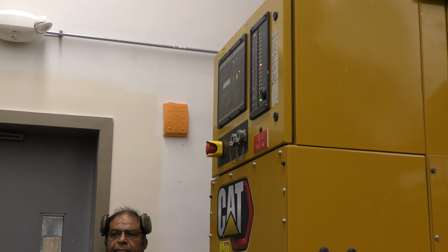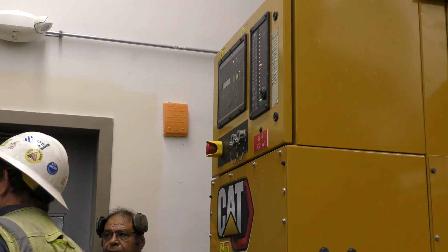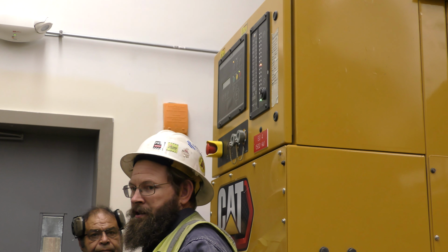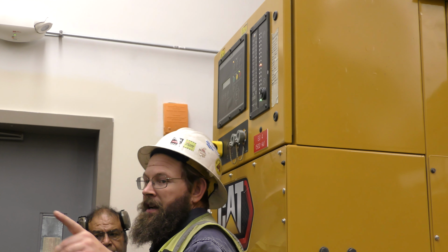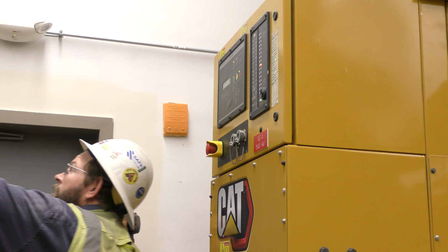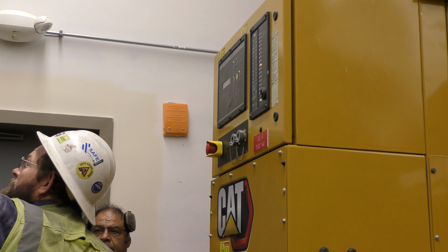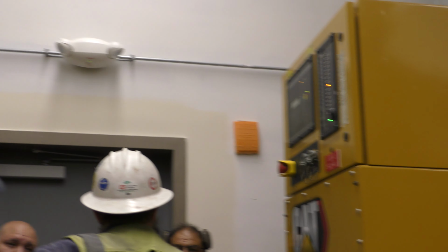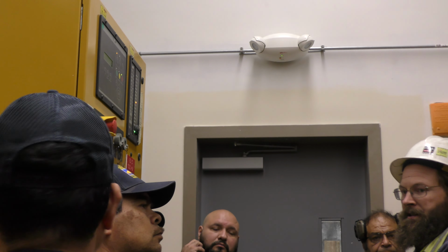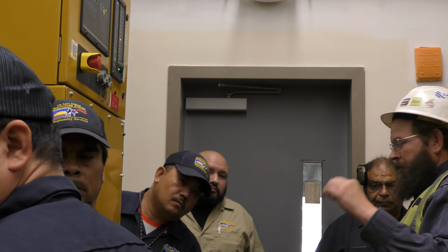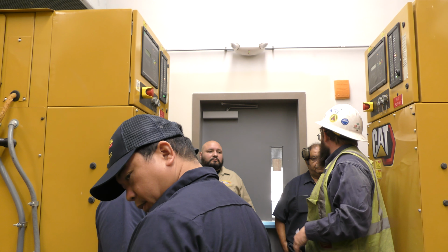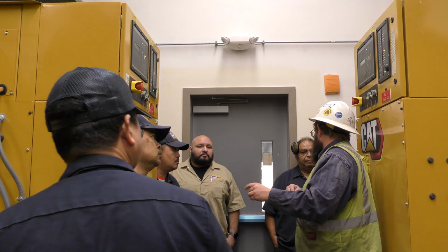You were asking earlier about if you lost AC power. If you were to lose AC power to the circuit, to the generators, your battery charger is going to go into alarm. So you're going to get AC fail on that. That's going to annunciate battery charger failure. So this alarm will be screaming at you. That light will be lit up, and you know, hey, something's wrong with the battery charger. You go to the battery charger, in front of that you'll see there's a green light on now, so everything's good. There'll be a red light that says AC failure. If you see that light, you know that you have no AC power from the generator. So that would tell you that you've lost that circuit.